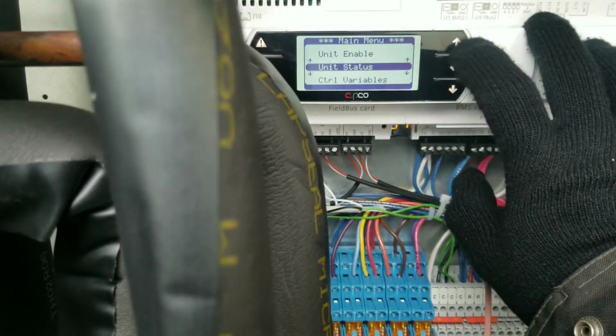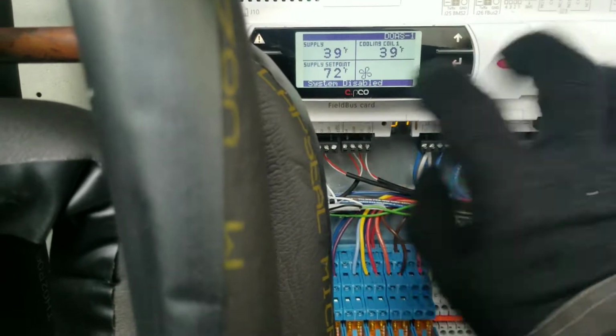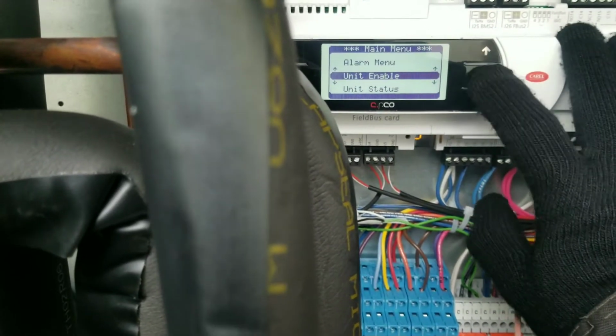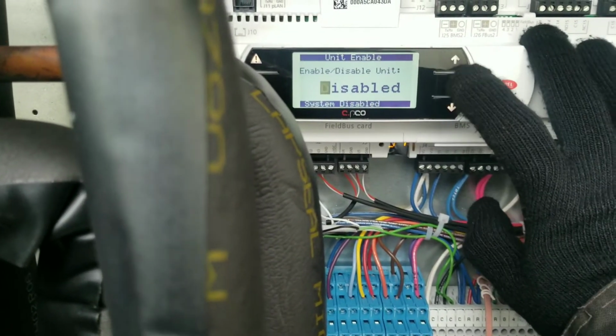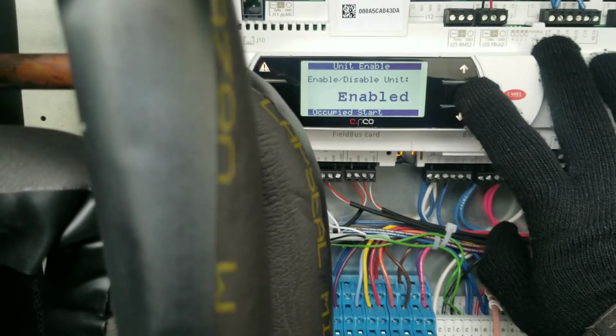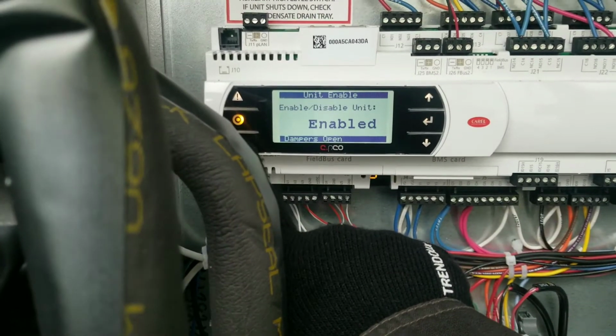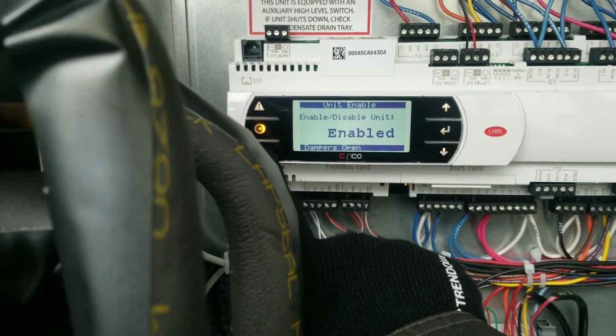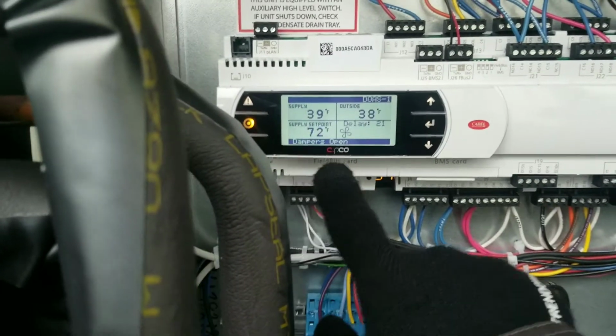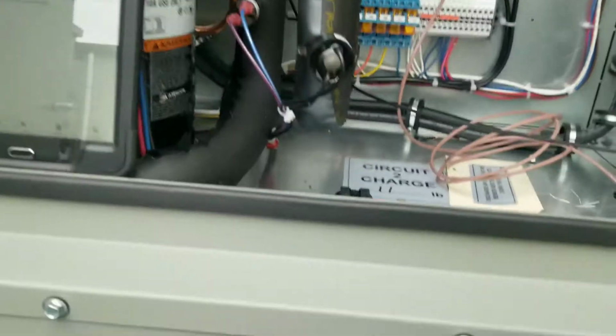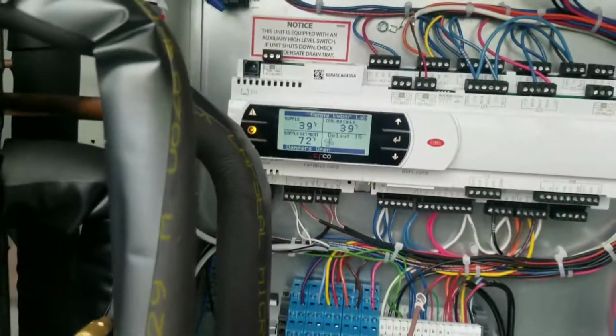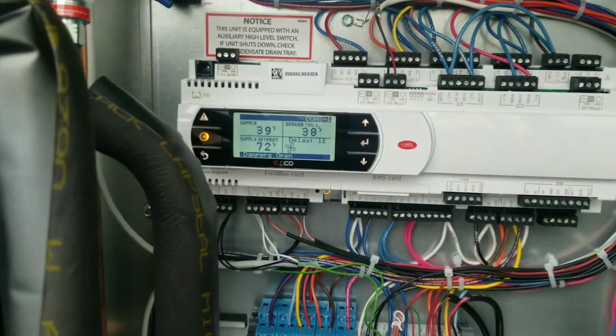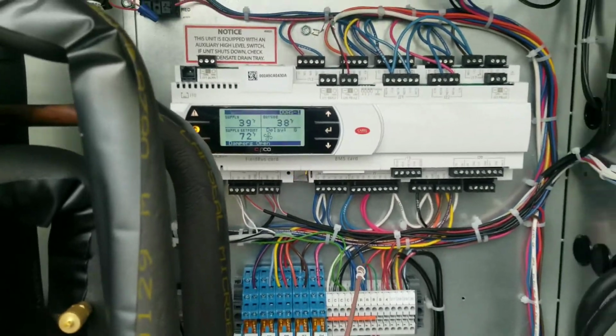So let's enable this guy. I can figure out how to do it. Maybe not. Unit enable, that's right. Enabled. The damper's gonna open first. I'm gonna bring my blower on. Let's see if this heat won't fire. Supply temperature is 39 right now, and my set point 72. I do have the fire alarm in test.